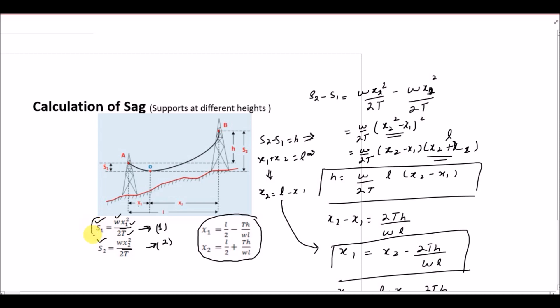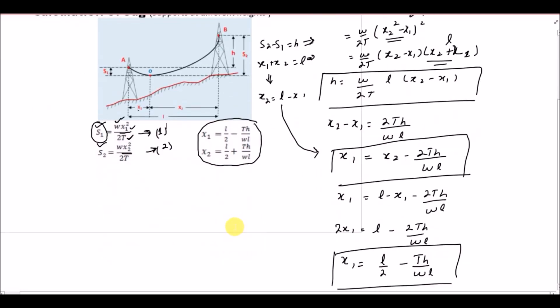Now we can calculate s1, the sag seen from tower A. We already know the weight per unit length, we now know x1, and we also know the tension value, so we can calculate s1. Similarly, we can calculate x2, which comes out to x2 = L/2 + TH over WL.